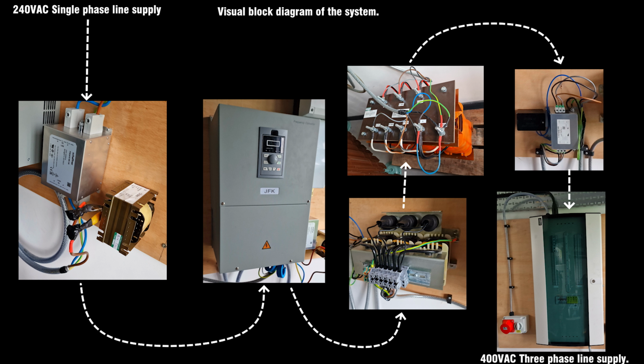Mine can be without a problem. Then inrush currents. There are a lot of misconceptions, like how a VFD can't just switch a load. That may be true with certain types, but that's generally not true for all of them. However, it is recommended to ask your manufacturer what type of current spikes you can draw. You can also add some capacitors to the DC bus to provide it with higher starting current capabilities. But again, it is highly recommended to take these up with the manufacturer of the drive, as they can advise you best on this application.